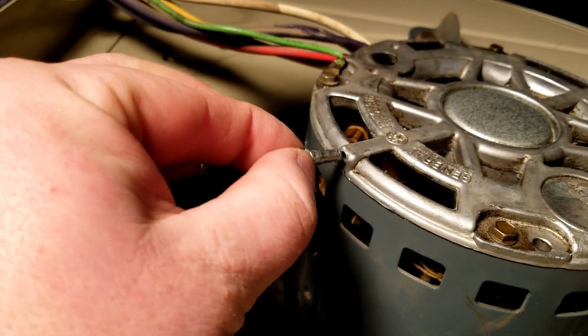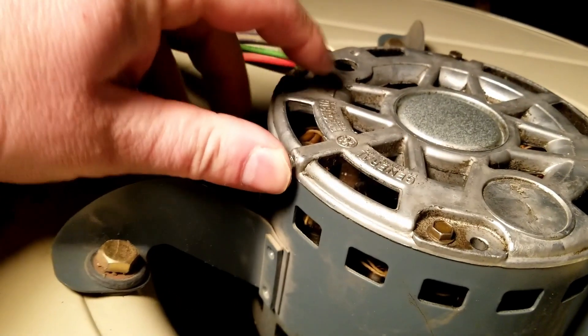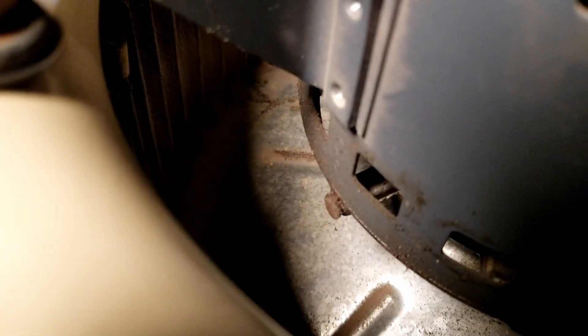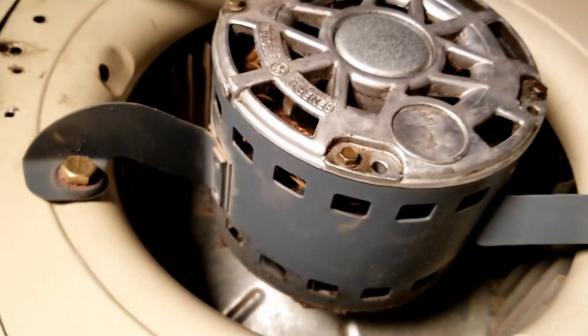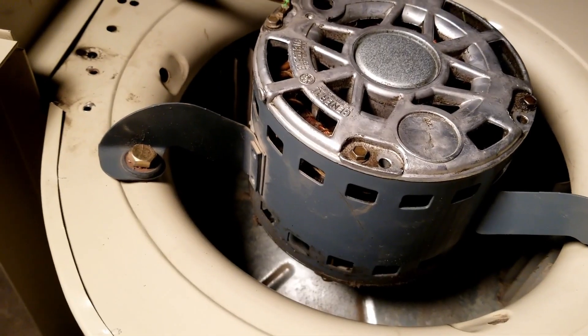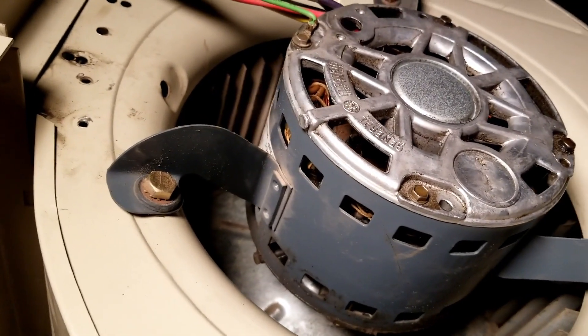And of course this one's made in USA, so it's an awesome motor. No wonder why it lasted 35 years. Well, flathead in there, and there's the little plug. So the HVAC guy said he oiled it and that's good, but that's the other plug right there. There is no sign that that plug was ever removed. Well there's another bearing in the front of the motor, so the HVAC guy only half-oiled the motor. That does not make Mongo happy. So somebody's gonna get a phone call in the morning.